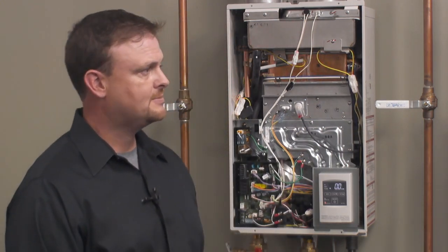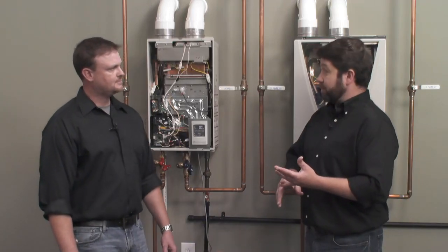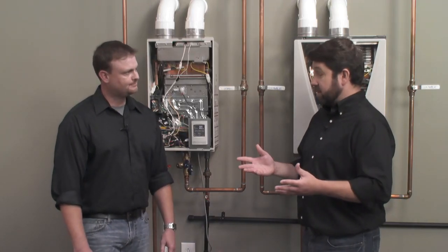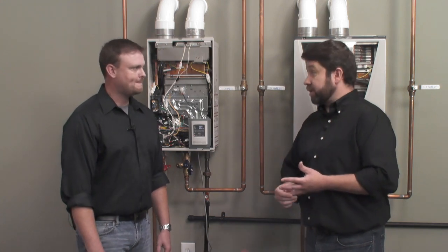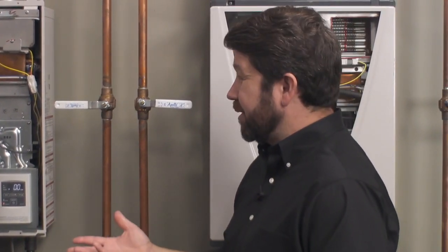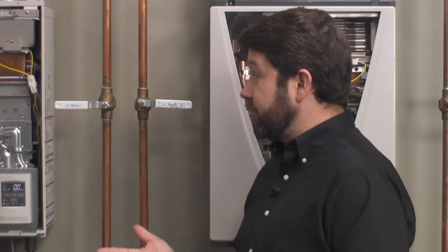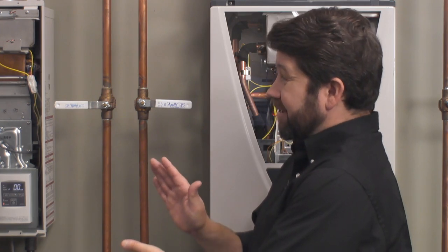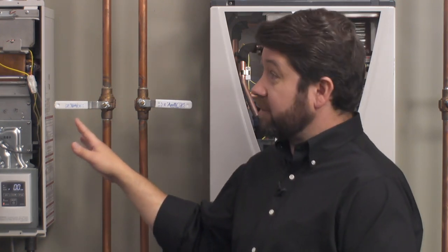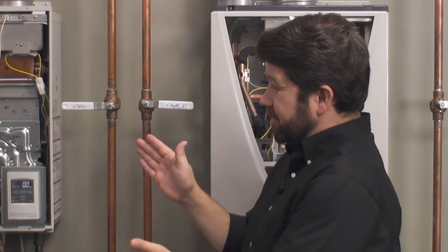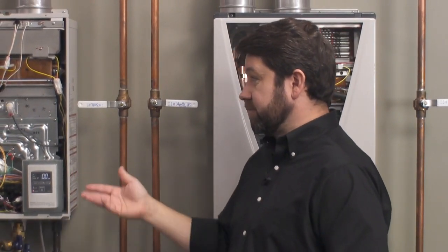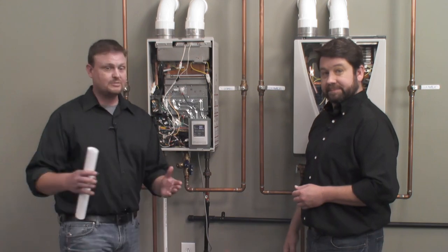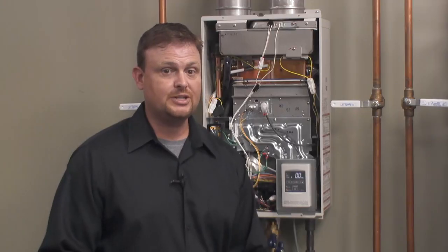Sizing is important, and one of the things we're going to be looking for is what's our maximum flow that we're ever going to need at one time, and then what's our coldest incoming, wintertime coldest incoming water temperature, and then what's the warmest temperature that we're ever going to want to deliver at. So if we were in Texas in the summertime, we wanted 110 degree water delivered, but our incoming water temperature might be 95 or even 100 degrees. There is a minimum temperature differential that we're going to look for because it's a minimum of 15,000 BTUs. So we want to make sure that we're going to generate enough demand to justify 15,000 BTUs. Yeah, because it ranges anywhere from 15,000 BTU up to 120,000 BTU.